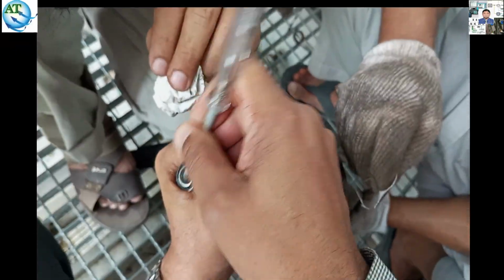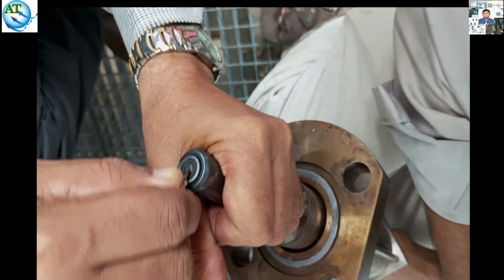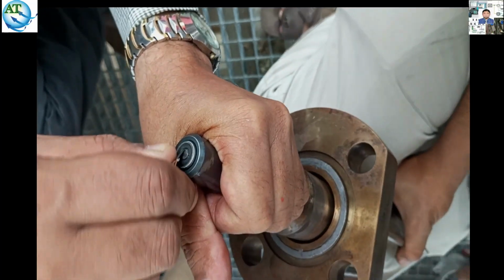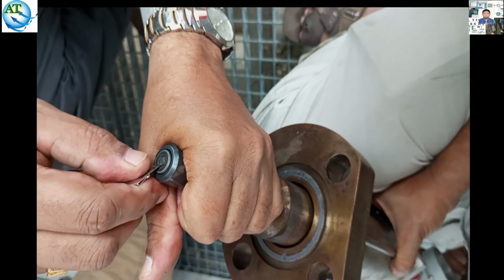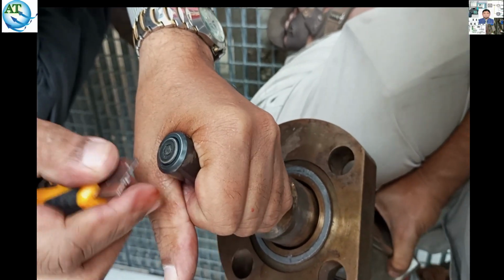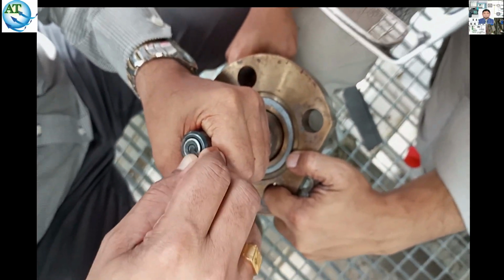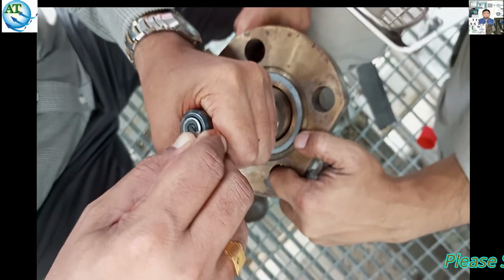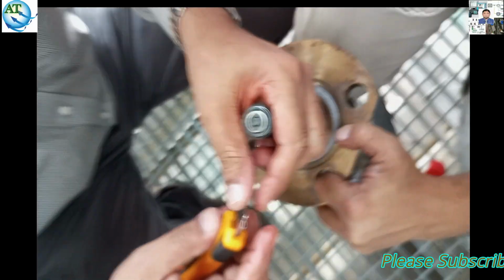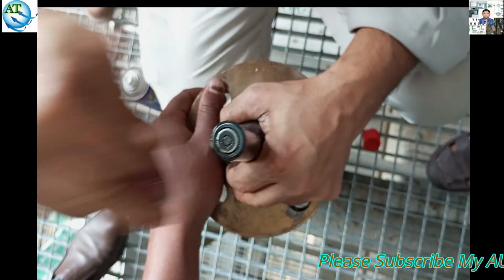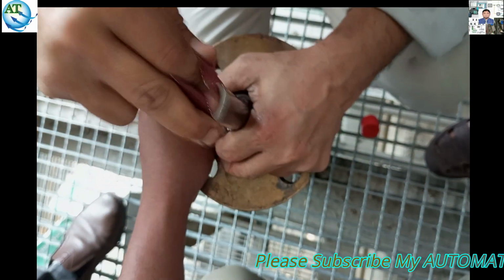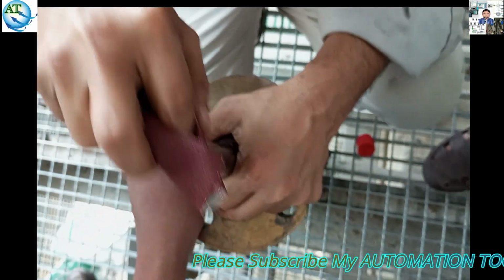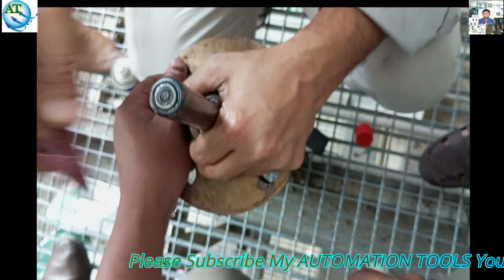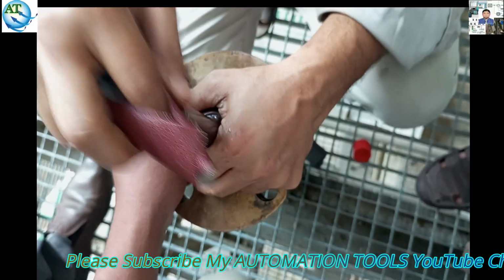Because we cannot keep failing to start the turbine again and again, the problem could be in igniter 1 or 2, or both. So we are trying to open the first one, clean it and check it. If we find it okay, we are trying to clean it using the papers. You see, we are cleaning this igniter.